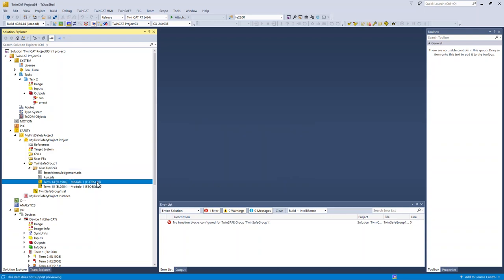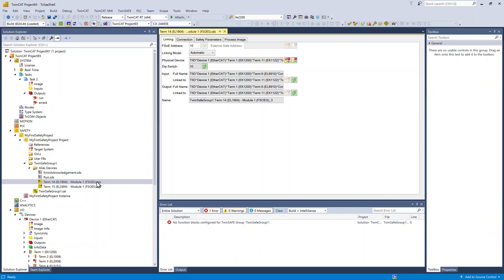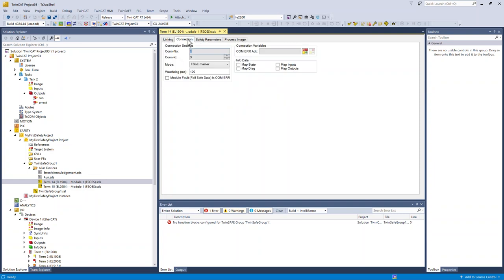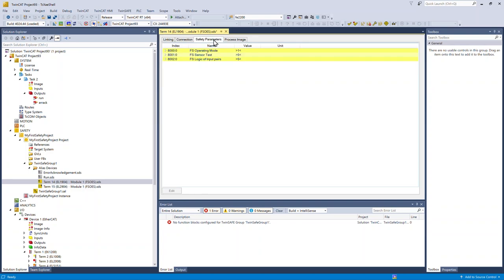Under the EL1904, the FSOE address automatically loaded from the DIP switches on the device. I like to activate info data, map the state of the device, the diagnostics, the inputs and the outputs. This makes it available to the standard PLC program.